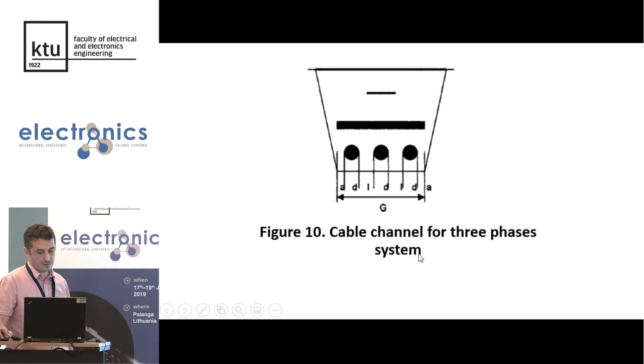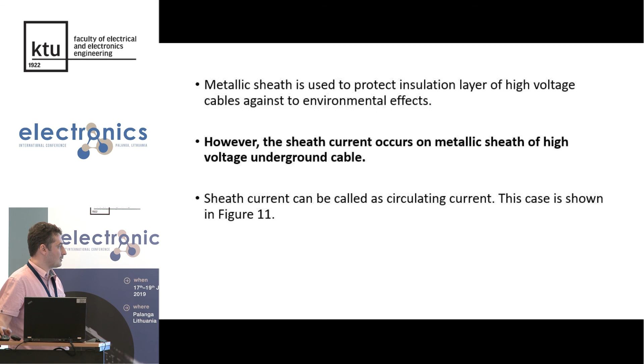Metallic sheath is used to protect insulation layer of high voltage cables against the environmental effects. However, the sheath current occurs on metallic sheath of high voltage underground cable line, and sheath current can be called as circulating current. This case is shown in figure 11. Circulating current, head of line and end of line. Sheath current generates sheath voltage on metallic sheath of high voltage cable. If sheet voltage is bigger than touch voltage limit value, electroshock risk occurs for human.